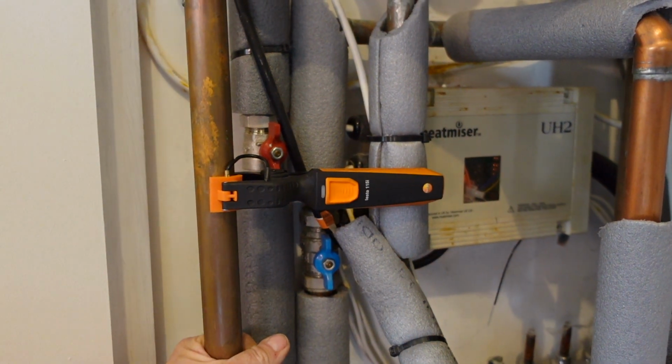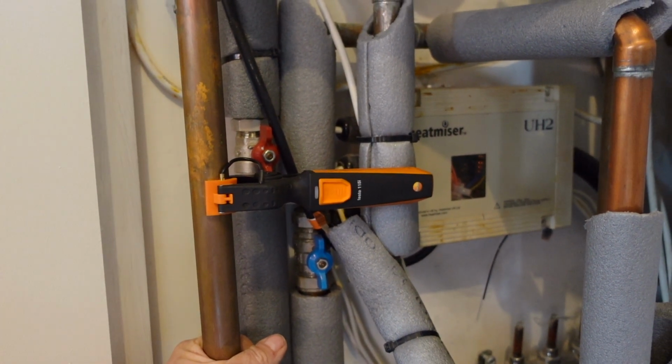We have got bottlenecks. We proved it, Miles, didn't we? We tried a little hot water cycle. Very quickly, the heating pump continued to run into the heating system, and after about 5 or 10 minutes, it was starting to pump cold water into the system. So it was starting to lose all its inertia of putting that energy into the system. I would have expected that pump to have shut down when it did a hot water cycle. So how does one control that? It's going to be some rejigging and some wiring. Maybe take a look inside the heat pump itself and see if there are relays or things that we can turn on by the controller that might help us.